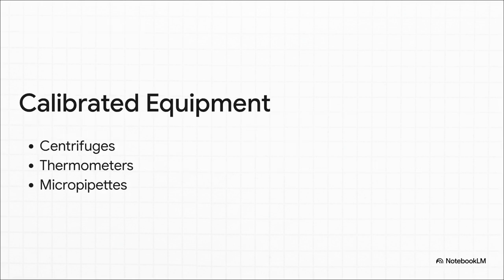And this applies to some of the most common tools you'll find in medicine. I mean, think about it. An improperly calibrated centrifuge could fail to separate blood components correctly, which could lead to a totally flawed test result. A thermometer that's off by just 1 degree could miss a critical fever. And micropipettes? These things measure incredibly tiny volumes. They could throw off an entire lab analysis if they dispense even a microliter too much or too little. Every single one has to be perfect.